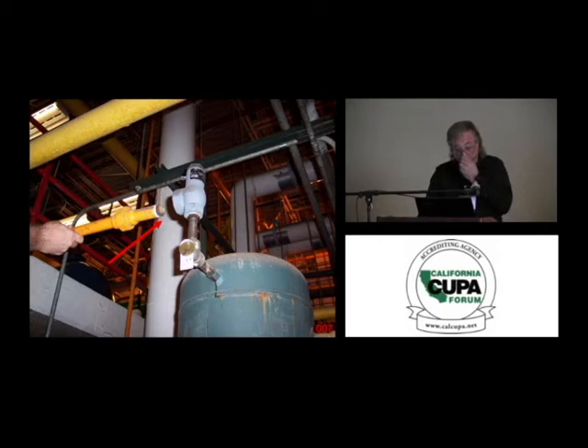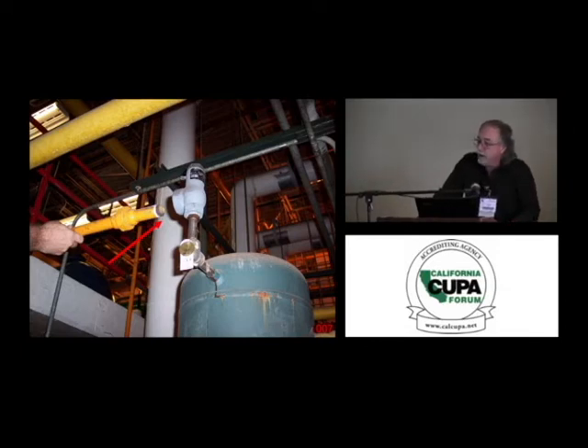This is an example of one of the relief nipples that broke. It was rattling when I went to inspect it, pulled on it, and it wasn't even connected anymore. We are having a problem with the nipples that support the relief valves, the three-way valves that house the relief valves, usually on screw compressors.